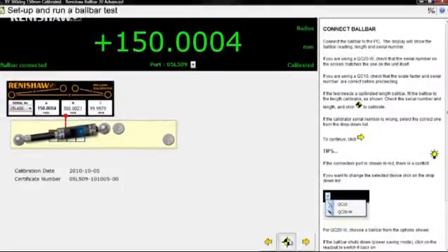To ensure that the calibration is good and that the device is repeatable, try removing the ballbar from the calibrator and placing it back in. The displayed reading should be unchanged. If you do see a difference, check that the pads on the Zerodur calibrator and the ballbar balls are clean and undamaged.